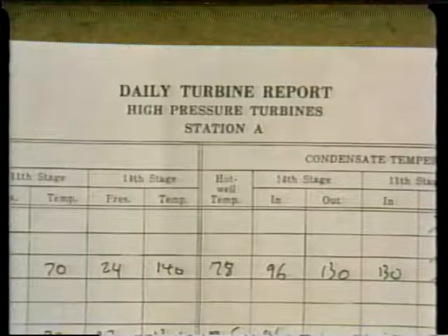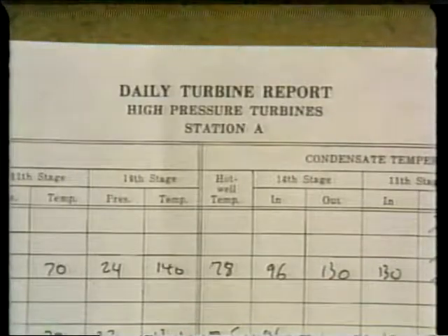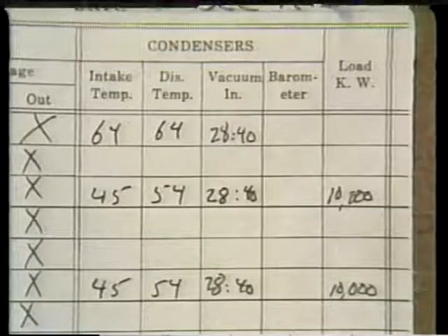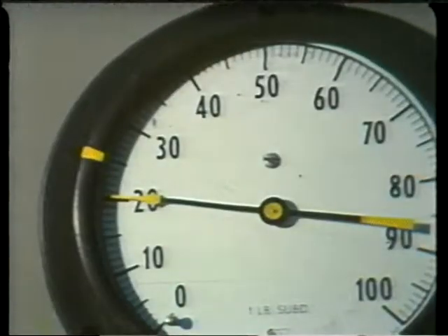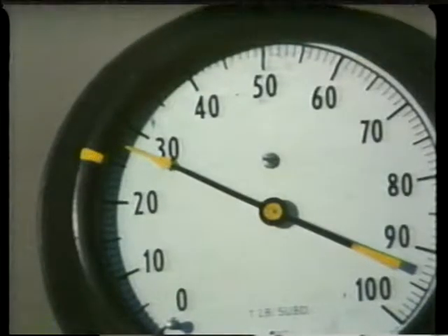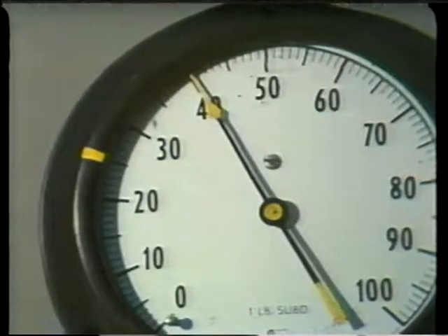Well, start with the operator and the operator's logs. Take a look at the readings that have been taken on that machine. What you're looking for is a trend. That is, a slowly changing reading or indication of temperature, flow, or pressure. Now, if you don't find a trend over the last 24 hours, you look at previous logs. A trend is sometimes slow to develop. So you pick a couple of logs from a month ago and compare those readings with the most recent ones.